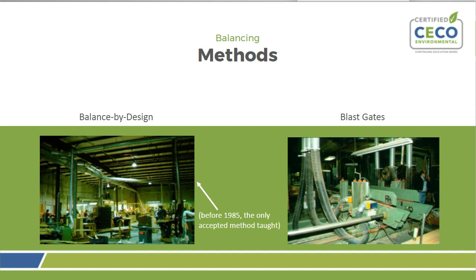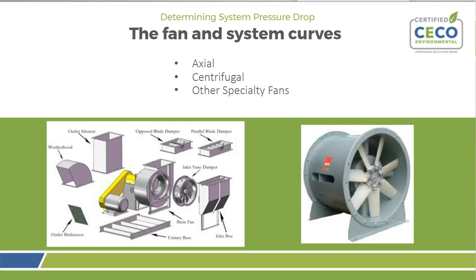So the alternative is a blast gate. With a blast gate, you can change the setting on the blade as to how far it extends into the duct. You can induce the static pressure you need to get only the volume that you need. And because blades can wear out, when you balance that system, you want to mark that blade, take a measurement, and record that so that when it's replaced, you know exactly where to set it when you go back.